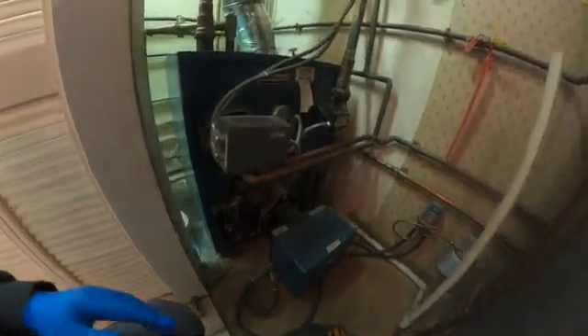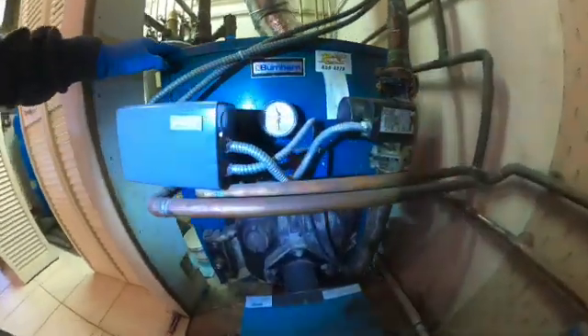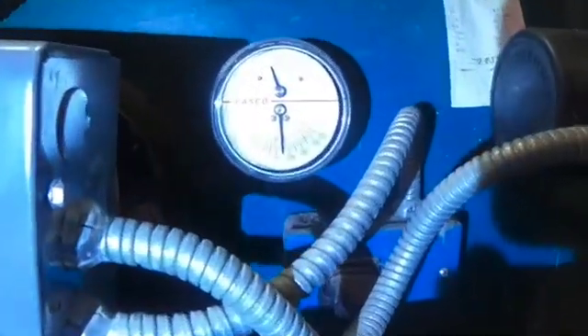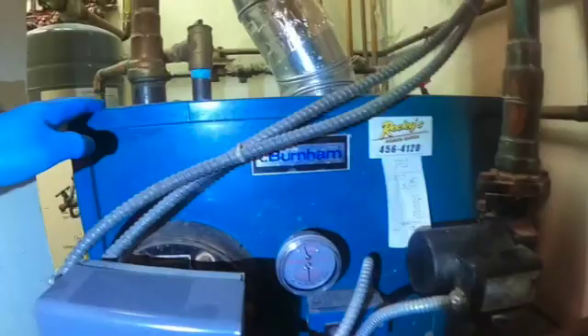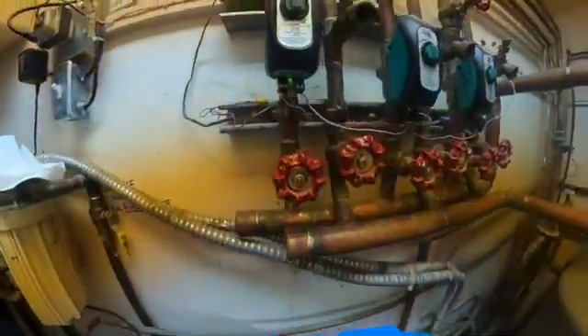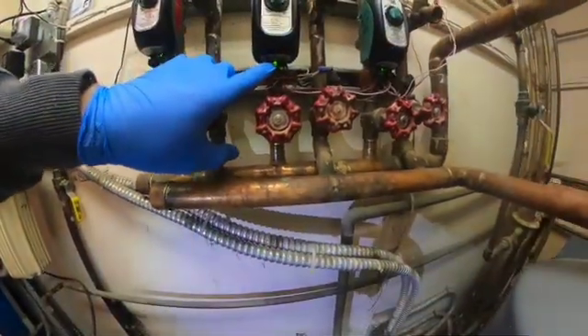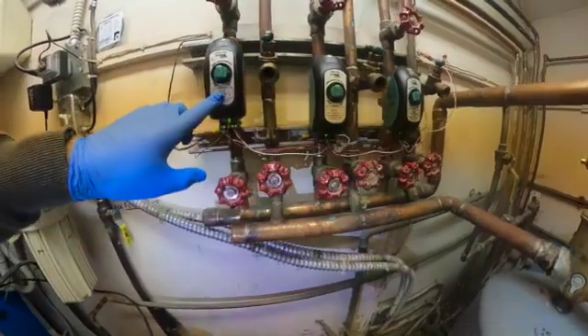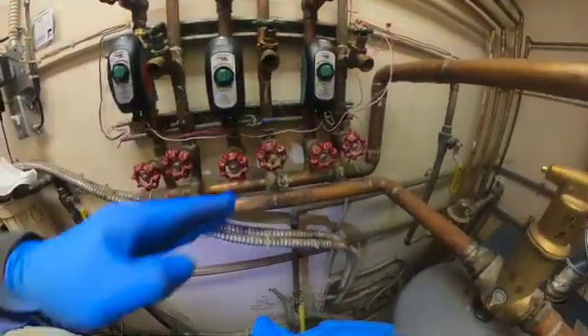Here's the boiler. Looks like it's up to temperature — we're sitting about 190 degrees. The zones are calling for heat and they're all open. You can see the little LED light on these Taco zone valves, and they're all in line going vertical, which means they're open.